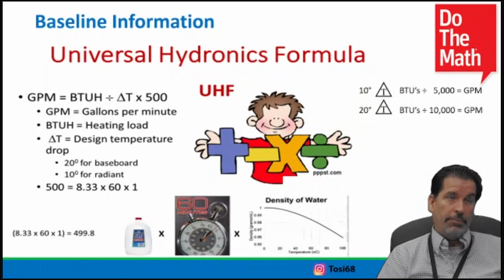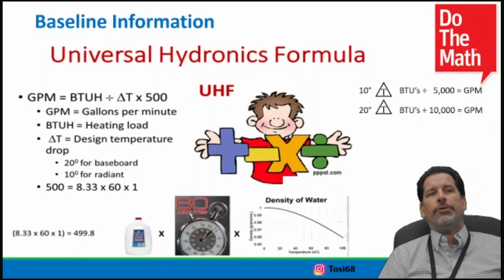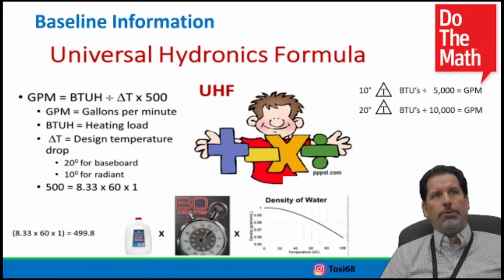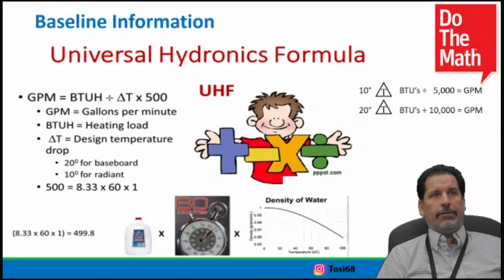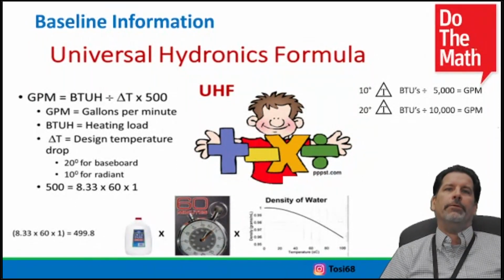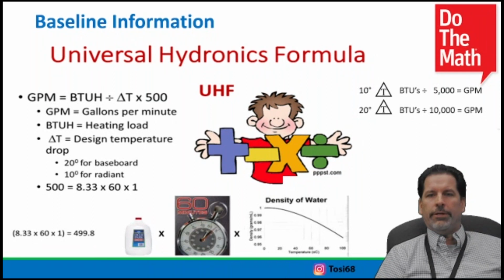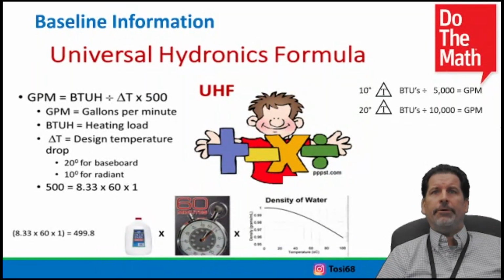Understanding exactly what is a BTU, right? British thermal unit. In my terms, better thermal unit, right? So the universal hydronics formula is where it's at. GPM equals BTUH divided by delta T times 500, right? BTU, we understand, H, hourly rate, down the bottom. You can see the delta T times 500. Where is that 500 derived from?